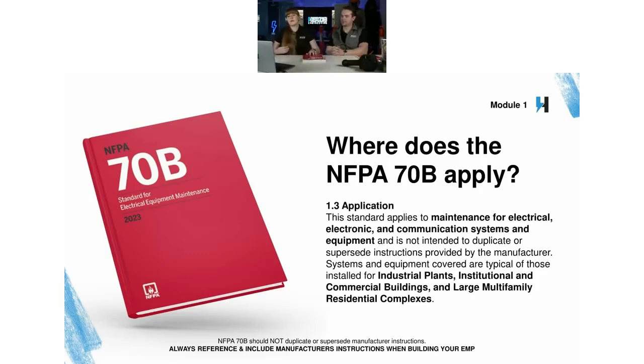The 70B applies to maintenance for electrical, electronic, and communication systems and equipment in industrial plants, institutions, commercial buildings, and large multifamily residential complexes. That's what it says straight from the code, but essentially it applies to everything except single-family residences, because that list is not all-inclusive. It says the electrical, electronic, and communication systems and equipment typically found in those areas mentioned, but that doesn't mean those are the only places this applies. Also note it should not supersede or duplicate the instructions provided by the manufacturer. This should be used in conjunction with whatever the manufacturer still requires for maintenance and testing. Just following this does not mean you're compliant, because it requires you to follow those documents as well. Very important note.